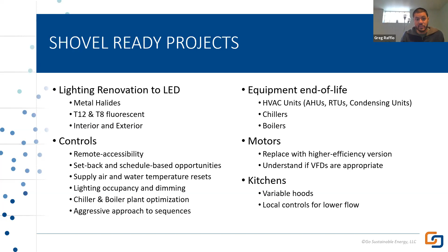Look for opportunities in your motors for higher efficiency, and find out if variable control with a VFD might be appropriate. If you have a kitchen, variable hood control and local controllers for lower flow when you don't need the same ventilation flow are worth exploring—talk to Melink or similar companies with good kitchen controls. These are good shovel-ready projects to consider.